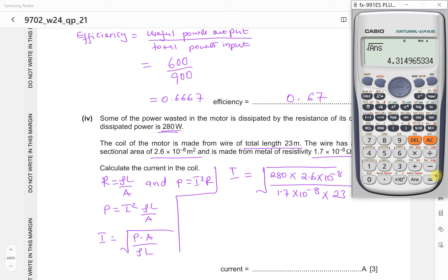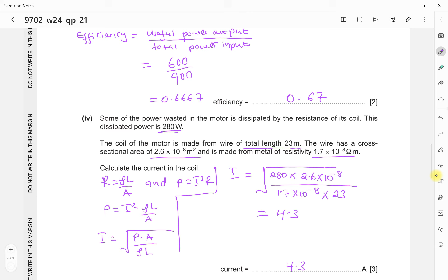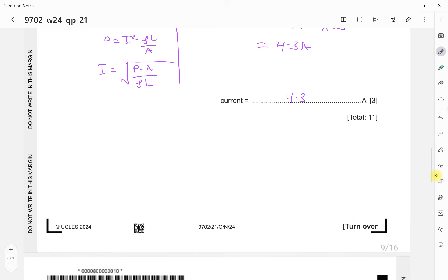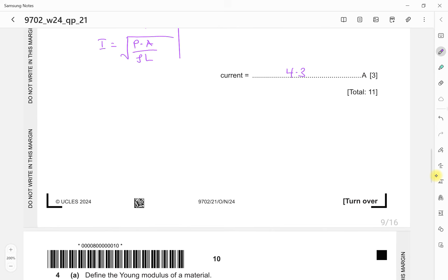When I make I the subject, I is going to be the square root of power times the area divided by rho times L. So the current in the coil is going to be the square root of the power, which is 280, times cross-sectional area, which is 2.6 times 10 to the power of minus 8, divided by resistivity, which is 1.7 times 10 to the power of minus 8, then times the length, which is 23. So I'll check the calculator. 280 times 2.6 exponent minus 8, I know that one cancels, divide by 23 times 1.7 exponent minus 8. Then we find the square root of the answer, which is 4.3. So the current is approximately 4.3. Okay, so that is going to be the current.